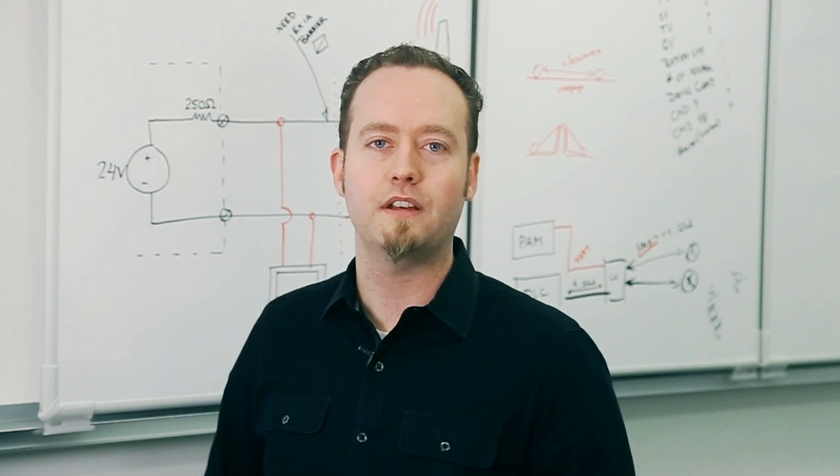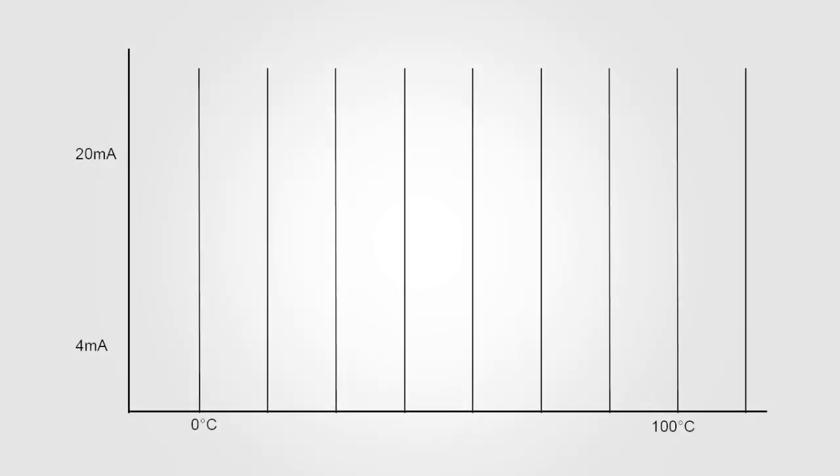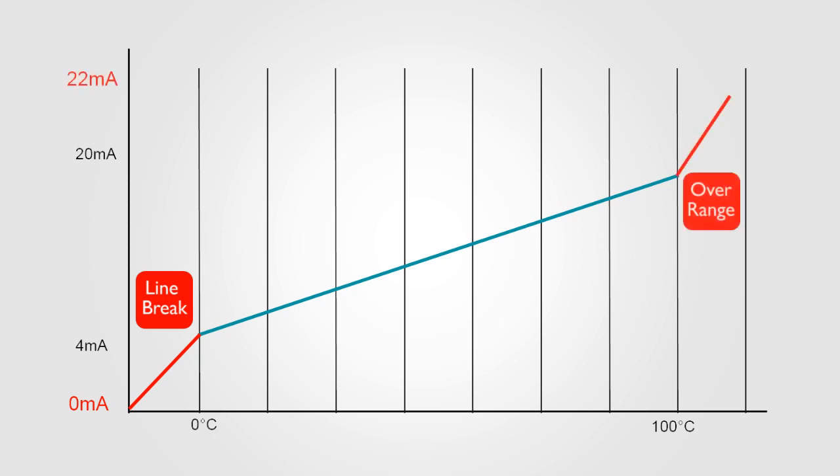When a transducer measures a value like temperature, it's converted to an electrical signal proportional to that temperature. If the transducer is measuring the temperature of a tank of liquid, which normally ranges from 0 to 100 degrees Celsius, it will output a 4 milliamp signal when the temperature is 0 degrees and 20 milliamps if the temperature is 100 degrees. A signal less than 4 milliamps is commonly used to indicate a fault condition, such as a wire or sensor break, while a signal higher than 20 milliamps indicates an overrange condition.